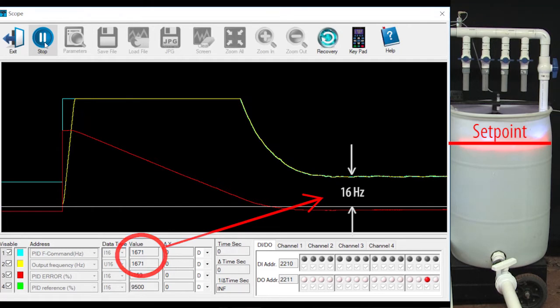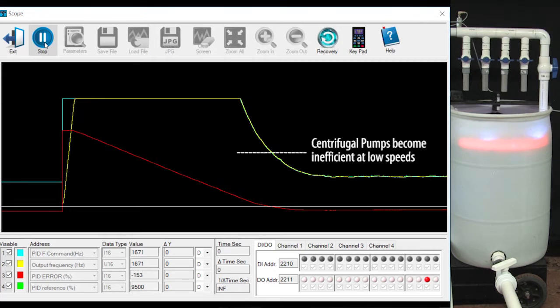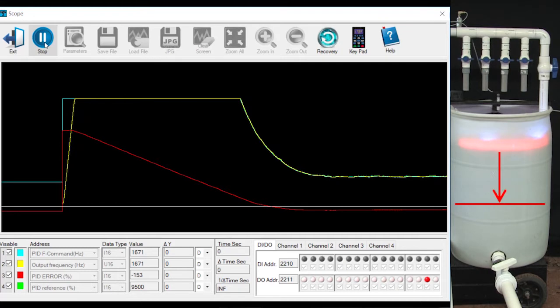But if we are just filling a tank, do we really need for the drive to be running at 16 Hz to maintain the water level? That's a lot of extra electricity and motor and pump wear and tear that really isn't accomplishing much. And since centrifugal pumps aren't real efficient at mid to low speeds anyway and will actually stop pumping altogether if the frequency gets too low, why not just turn the motor off when the PID commanded frequency starts to get small, and then let the water level drain to some lower level before turning the motor back on.